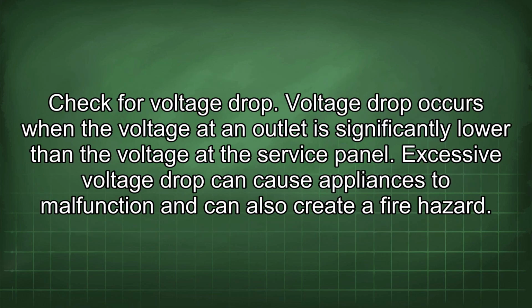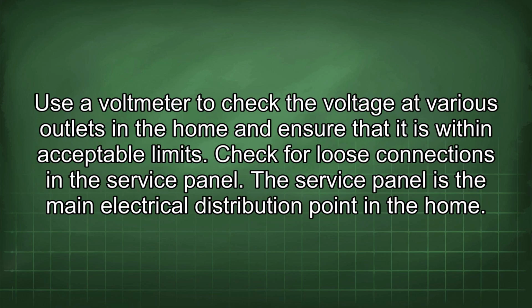Check for voltage drop. Voltage drop occurs when the voltage at an outlet is significantly lower than the voltage at the service panel. Excessive voltage drop can cause appliances to malfunction and can also create a fire hazard. Use a voltmeter to check the voltage at various outlets in the home and ensure that it is within acceptable limits.